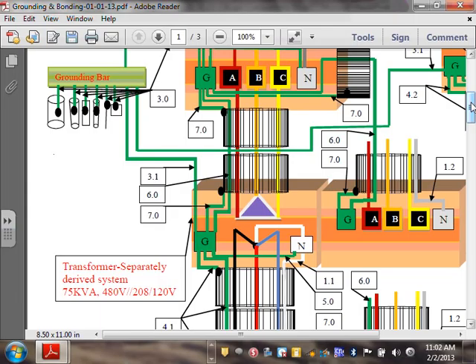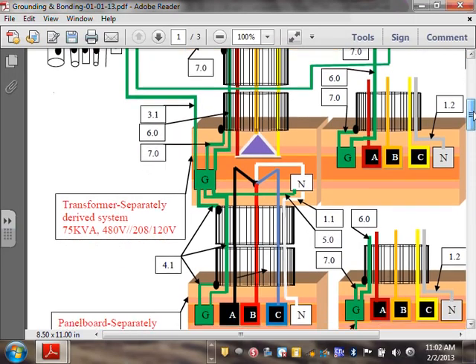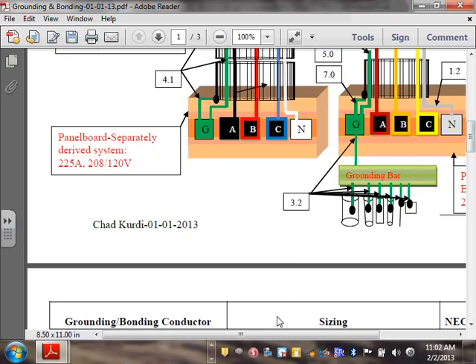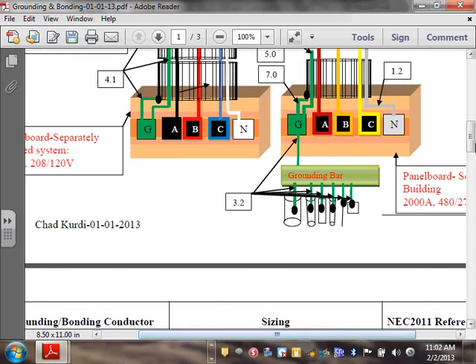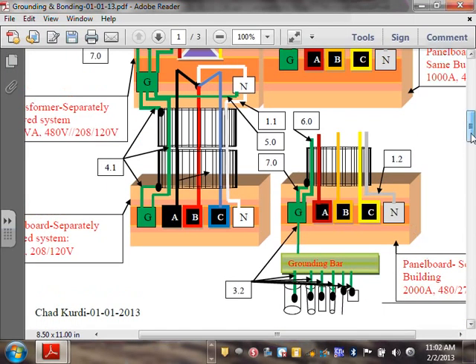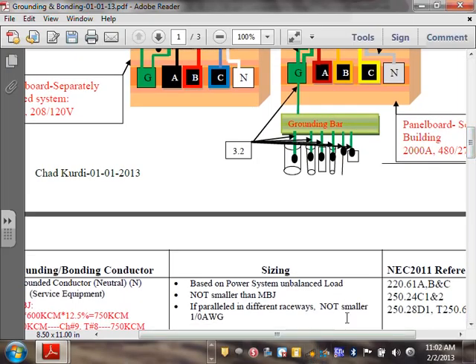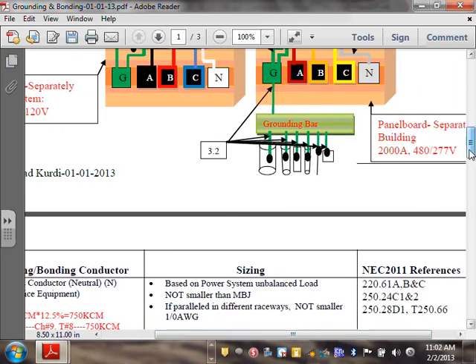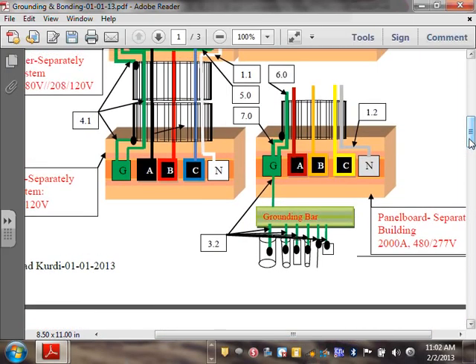They're separate buildings. Okay, so let's go to the scenario. Here's my scenario. This scenario, guys, because it's easier. Now, I went to a separate building, and I'm still pulling. I went with a 2,000 amp. This has to be switchgear in this case. 480/277. Went to a separate switchboard or switchgear, and I need to do bonding and grounding.